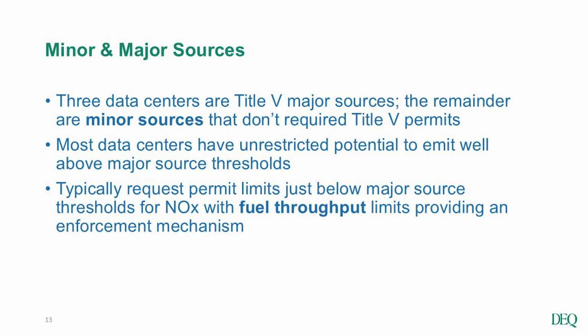Typically we do that by fuel, limiting the amount of fuel they can consume. So that entire collection, whether it's 270 gensets or 300 or however many they have, we limit those units to a certain pool of fuel, which we use to calculate the emissions that set the permit limit. That gives us a good enforcement mechanism — by tracking how much fuel they're using, we can know what their emissions are.